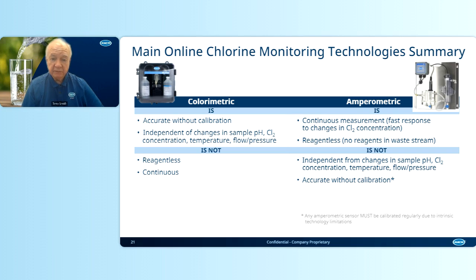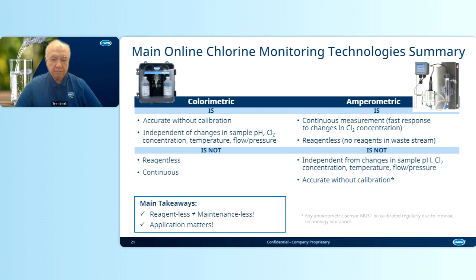Amperometric is continuous measurement, fast response to changes in chlorine concentration, and it has no reagents in the waste stream. It is not independent of changes in sample pH, chlorine concentration, temperature, flow, and pressure. And it is not accurate without calibration. It must be calibrated at least weekly. So, main takeaway, reagentless is not maintenanceless. The method matters, application matters.